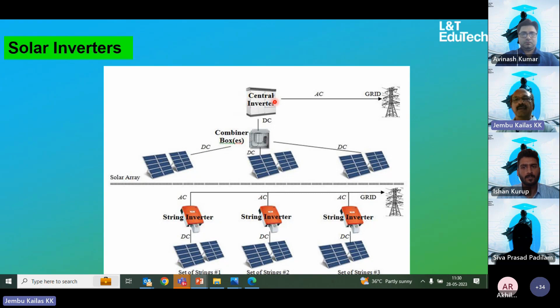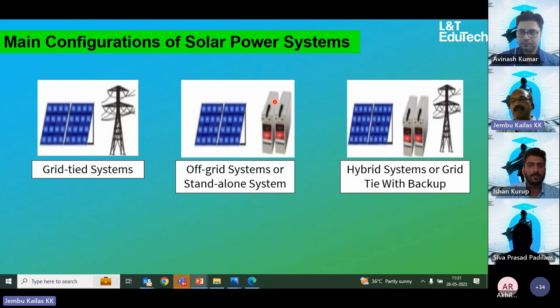So all these things this inverter will take care of, and also reactive power injection, this inverter will take care of. Suppose for a voltage dip where the inductive reactance is very high, then it will inject capacitive reactance, and it will still maintain the grid voltage level. Voltage sag and all, it will manage. So today's inverters have a lot of features. So that is the main configuration of the grid, I told you about grid tied systems. You have got a directly grid tied system, an off grid system, that means it's as good as a standalone system, and a hybrid system. So different types are there.